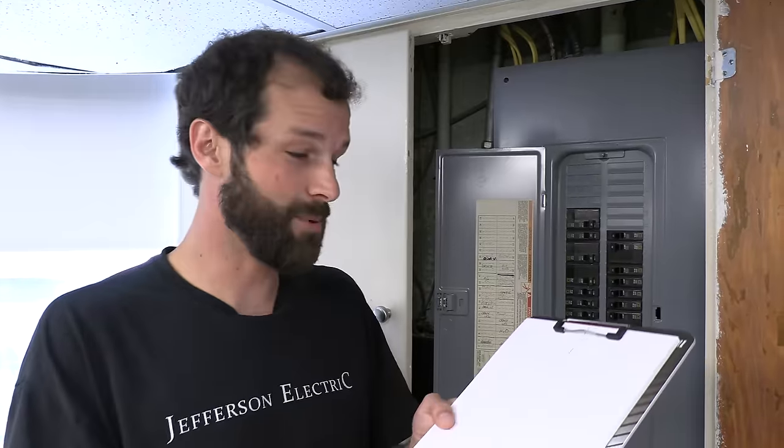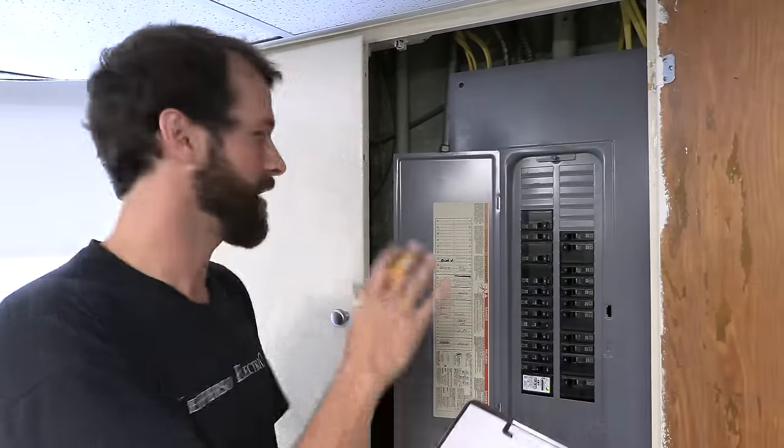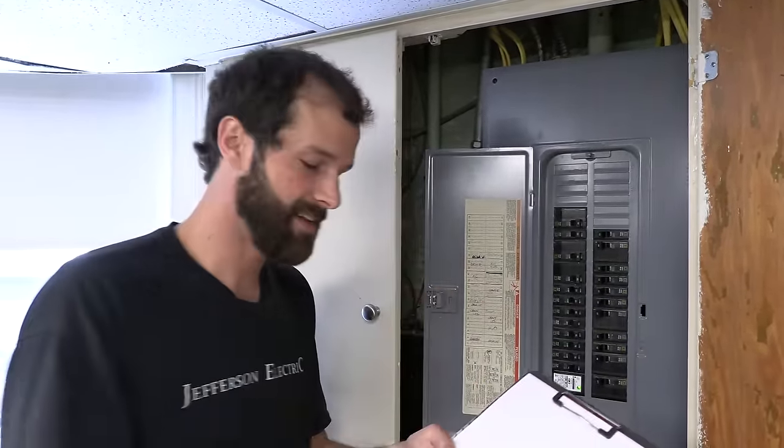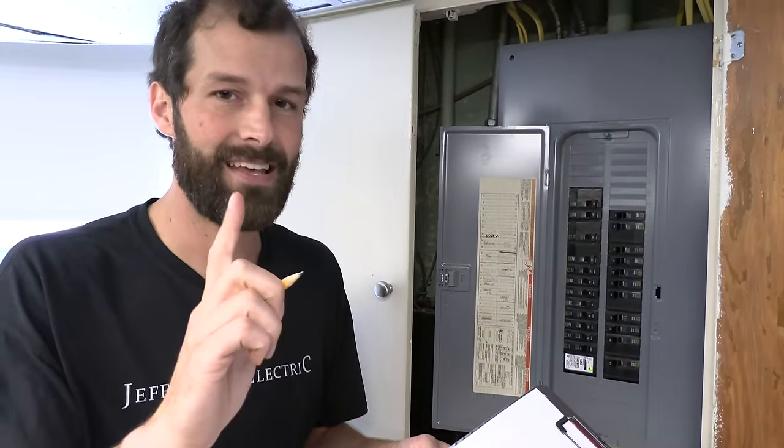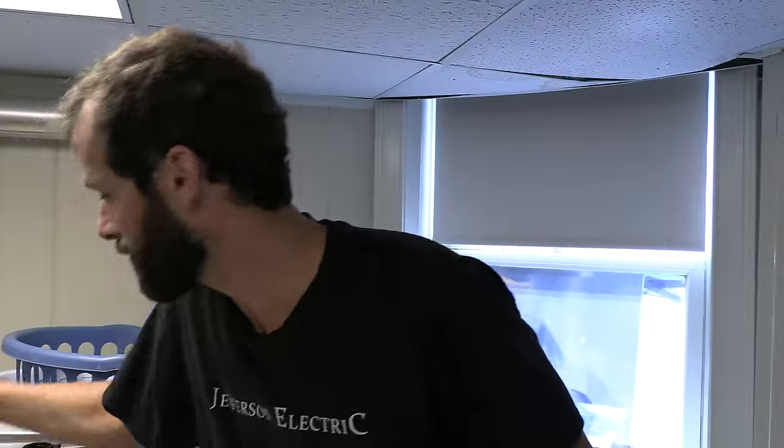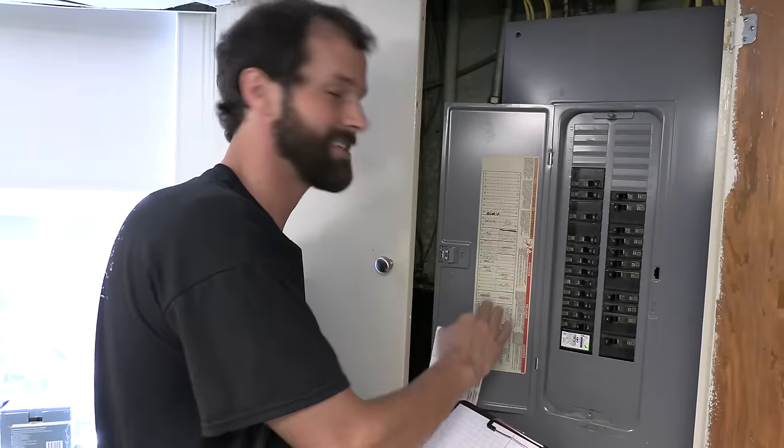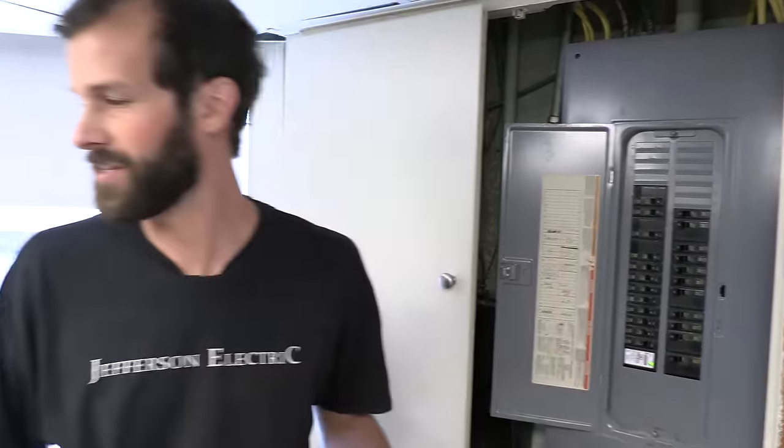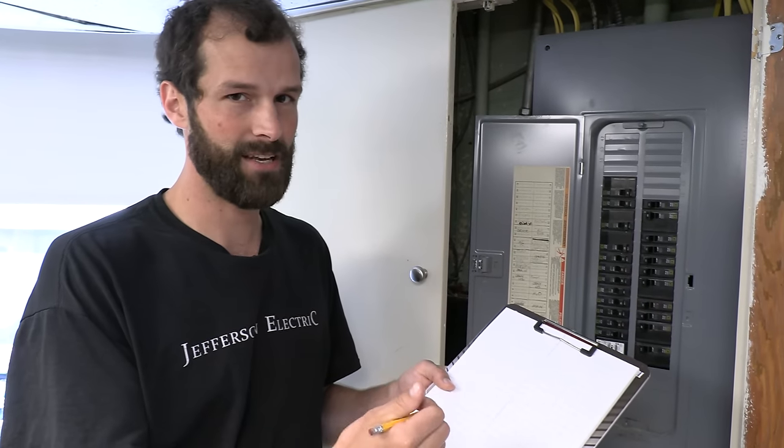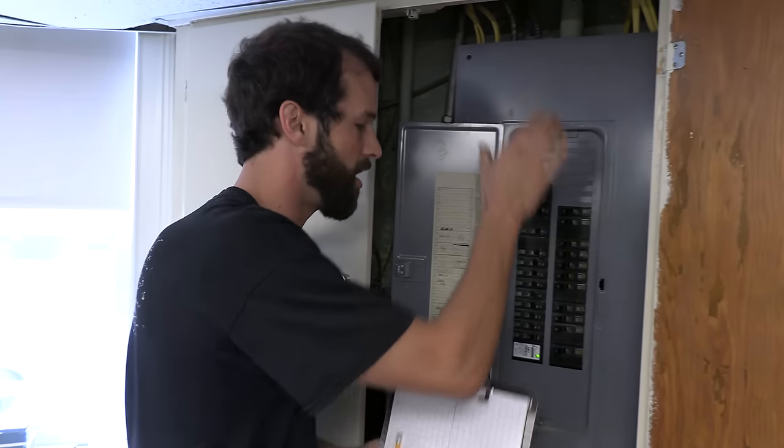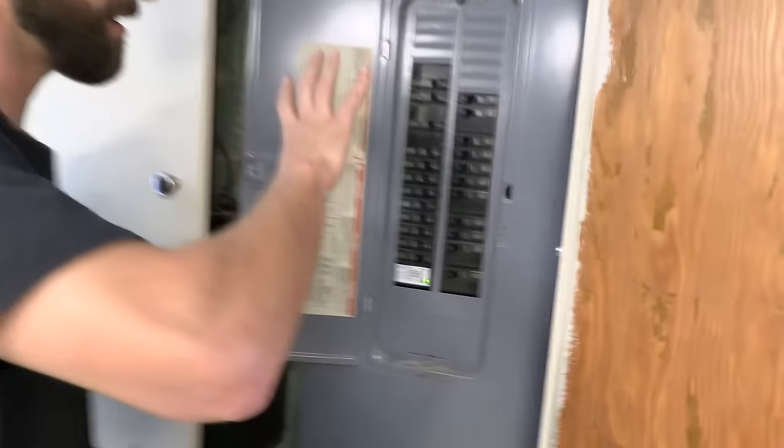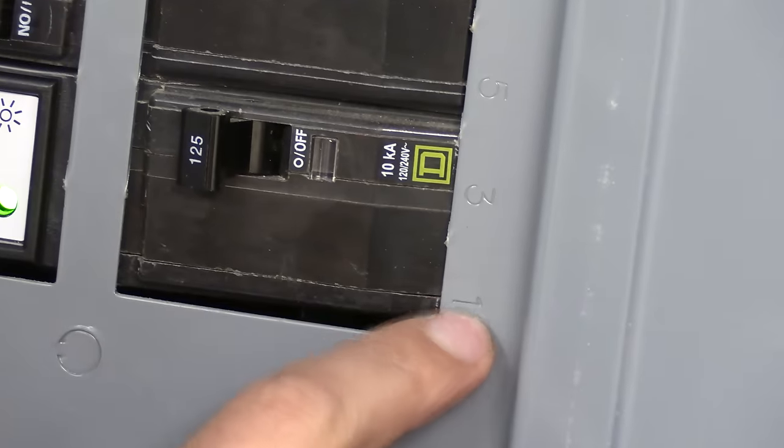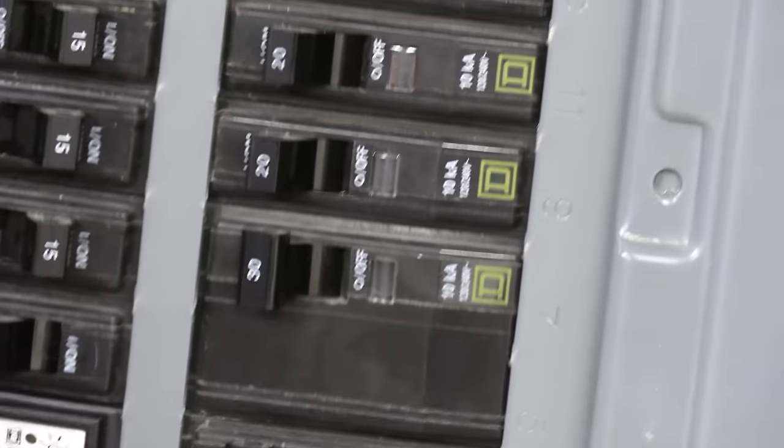I'm going to start using my coach's clipboard to take copious notes on what I find. And I'm definitely not writing on the panel schedule yet until I've consolidated and verified all my information. And then I'm going to apply a nice, new, clean set of labels like this. I'm going to go over what's existing once I've consolidated all the information. But for now, I'm just taking notes. Let me tell you one more thing. Panels are typically numbered. The numbers can be hard to read because this panel is in the inverted fashion, which is code compliant and totally fair. One is down here. So it's one, three, five, seven, nine, eleven, and so forth. Two, four, six, eight, ten, and so forth.